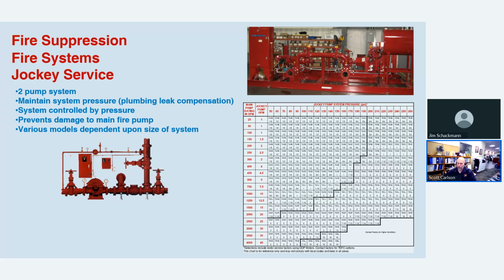Well, while the system remains dormant, you'll have leaks in the system, whether it's a drip on some floor somewhere or a check valve that's pushing water back into the source tank. Whatever the case may be, you need to have a small higher pressure pump to recharge the piping where the sprinklers are. And regenerative turbine pumps are really good at that. They just turn on once every couple hours for 10 minutes. The system's recharged, and it's good for however long it takes for that pressure to go back down again.